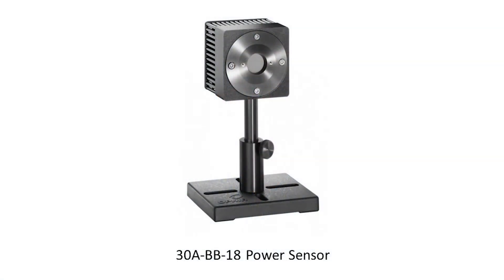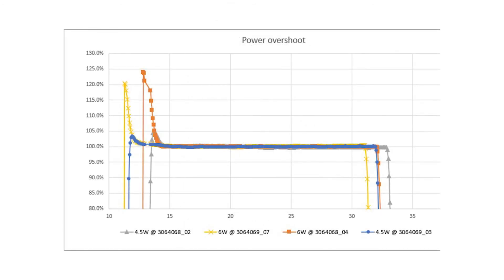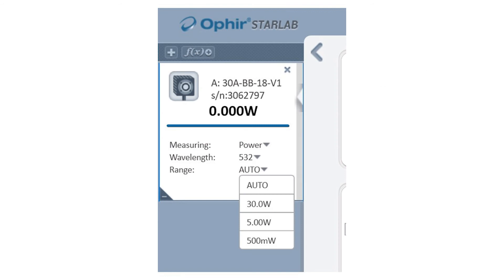The second case has to do with overshoot. This time, a customer was measuring several watts of power with a thermal sensor — in this case, the Ophir 30ABB18. As the power of the beam changed, they found that sometimes they saw a bad overshoot until the reading stabilized at the new power, and other times they did not see such an overshoot. So we again asked for a data log file to help us diagnose the issue. The power ranges defined in this sensor are 30 watts, 5 watts, and 500 milliwatts — and, of course, auto range.